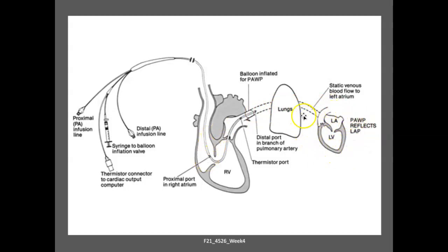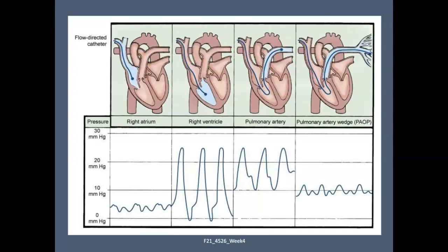So this is a better schematic diagram of what it's actually looking at compared to the previous one. And so these are the different waveforms. As the physician is putting the catheter through and you've got the catheter connected to your monitor, you're going to see these different waveforms, and that's how the physician understands where they're at as they're advancing it.